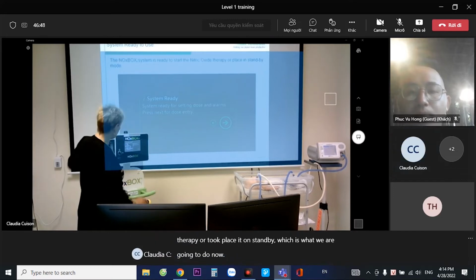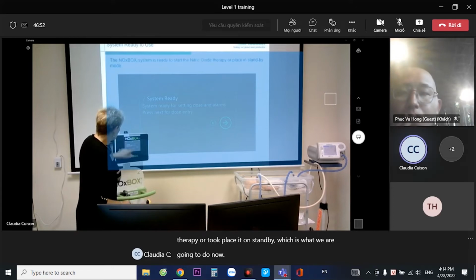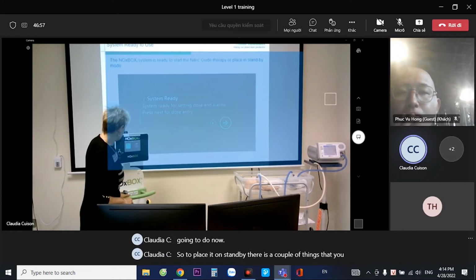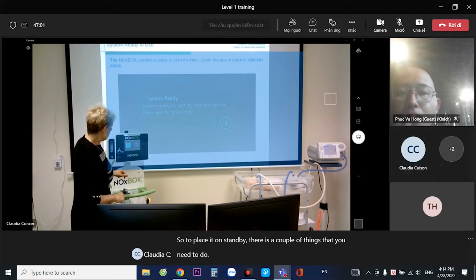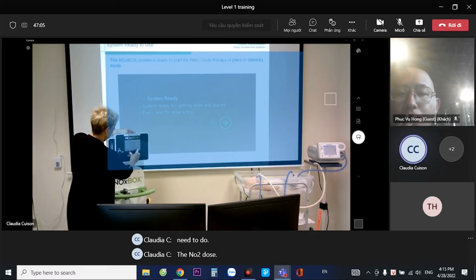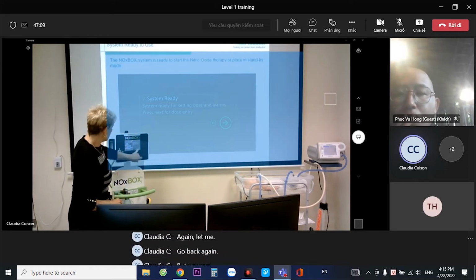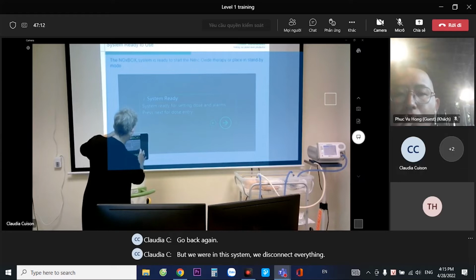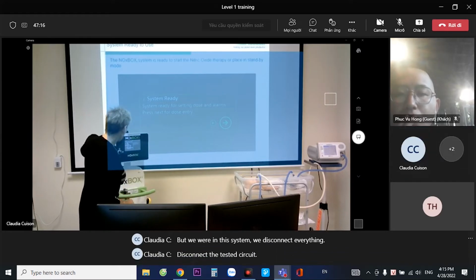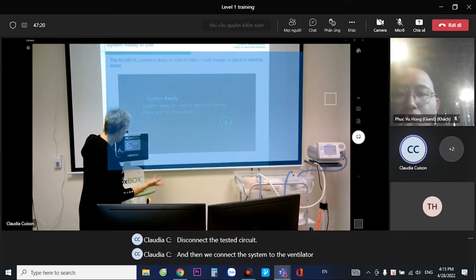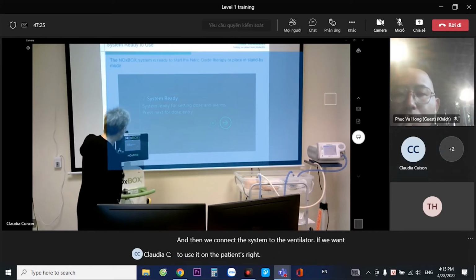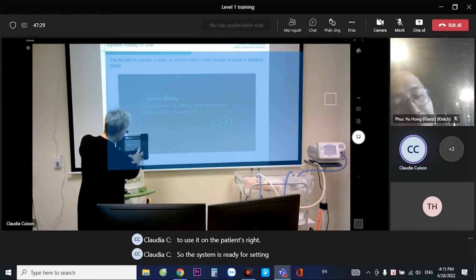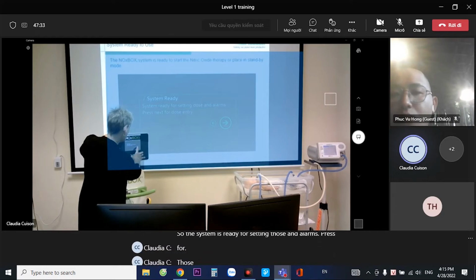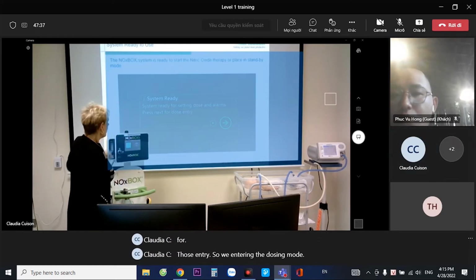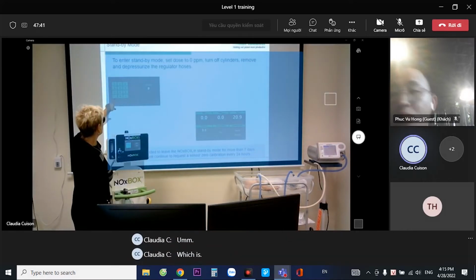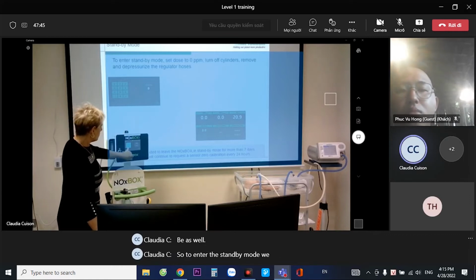or to place it on standby, which is what we are going to do now. So to place it on standby, there is a couple of things that you need to do. The NO dose, again, let me go back again. So we were in this system, we disconnect everything, disconnect the test circuit, and then we connect the system to the ventilator if we want to use it on the patient, right? So the system is ready for setting dose and alarms. Press for dose entry. So we're entering the dosing mode, which is this mode. So to enter the standby mode, we set the dose to 0.